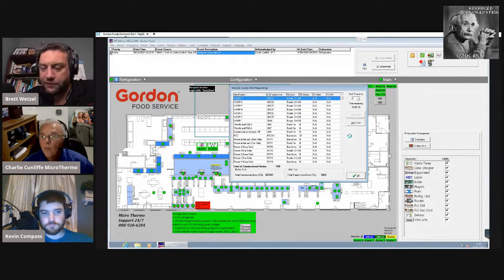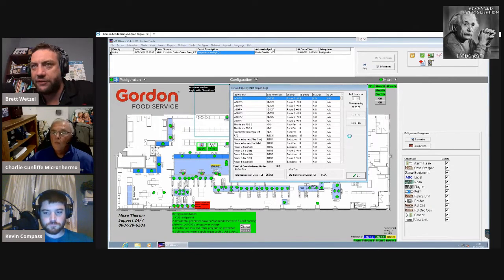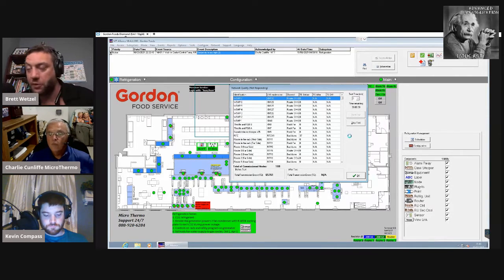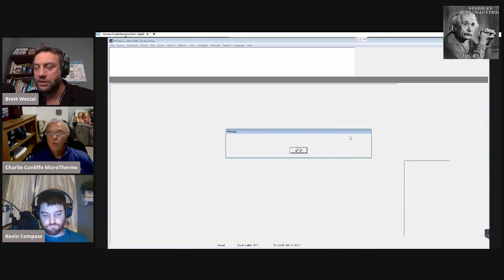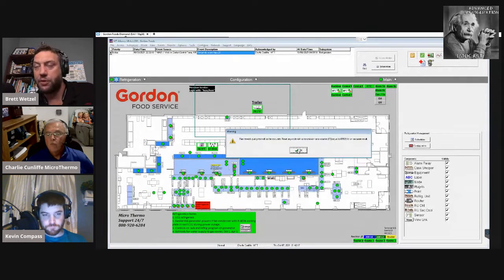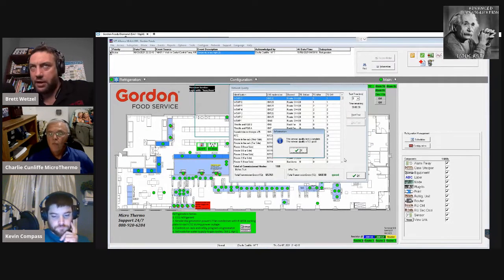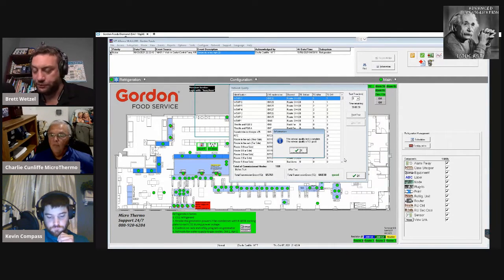So we were talking about voltages. The reason, guys, why that's really important is, most boards have a certain range that they can be high and low. It's important to pay attention to that, because if it does go lower than what it's supposed to, a lot of times you'll start having problems on your network, because the voltage will be too low. Or if you have an input board, you could have sporadic numbers reading on there, because it's changing your voltage, which is changing the reading that it's supposed to be getting back to the controller for your temperatures.